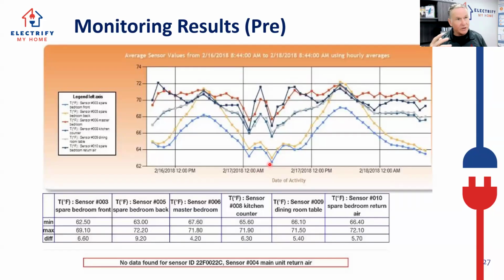And what we found is when that system was running on that one zone on the end, it was causing it to have to go into defrost more for whatever reason. So we called the manufacturer rep out. We called the rep from the distributor out. They both came out and looked at it and they were scratching their heads. And they go, well, let's just start changing parts.